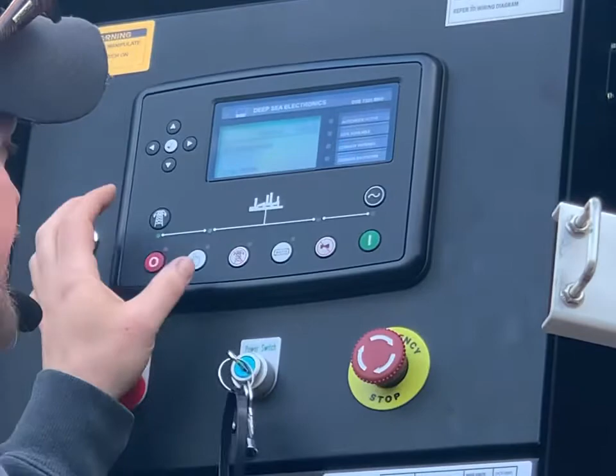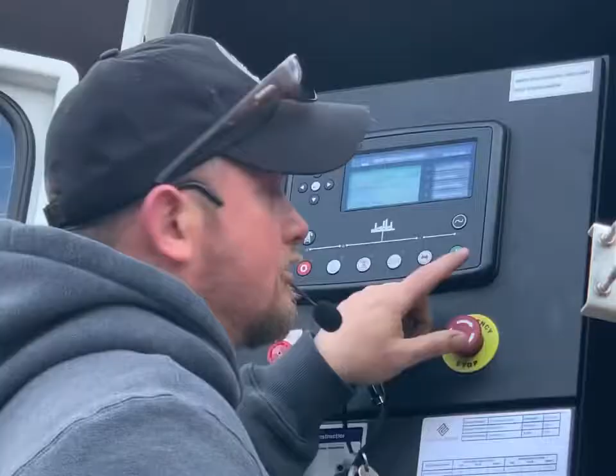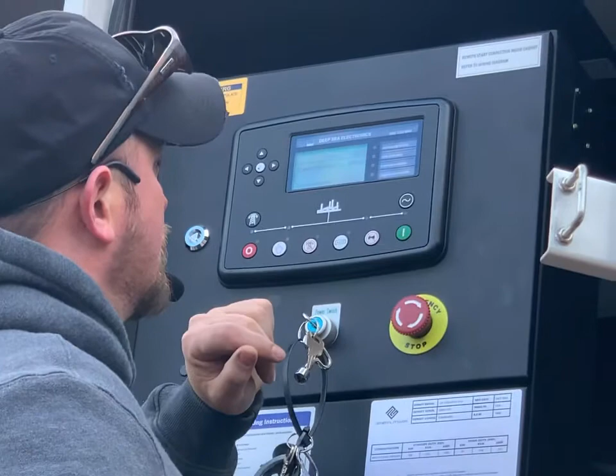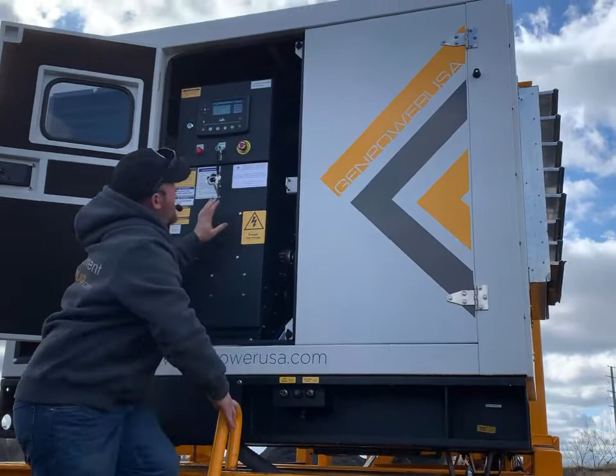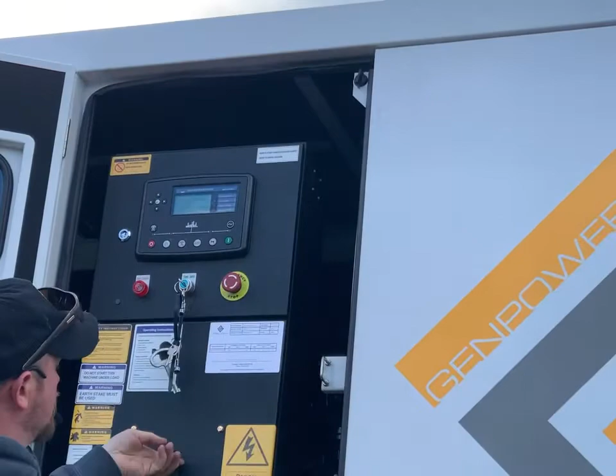After a minute it'll warm up and tell you that the generator is available. What you'll do from up here to get the power from the generator to go back to our control panel is just flip this switch. You have to wait for the generator available light to come on, which it is now. Now we've got power going back to our main panel.